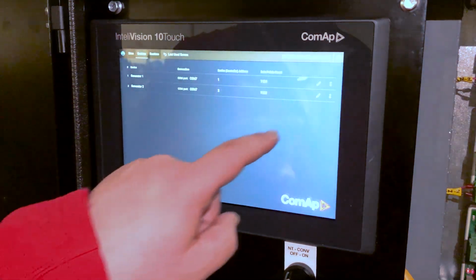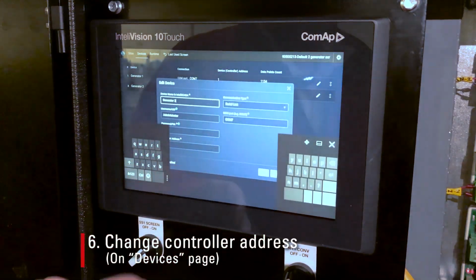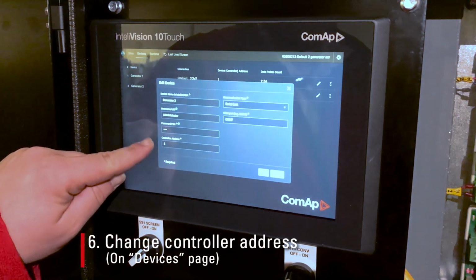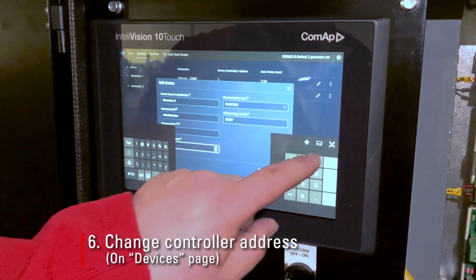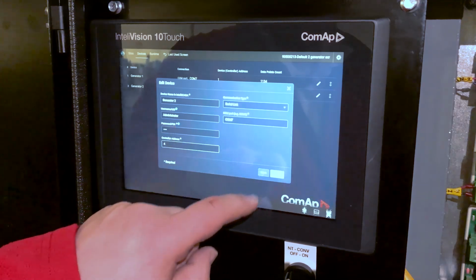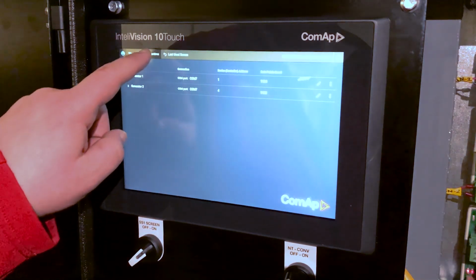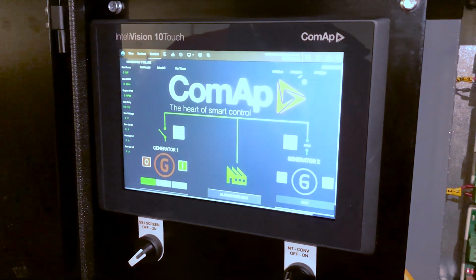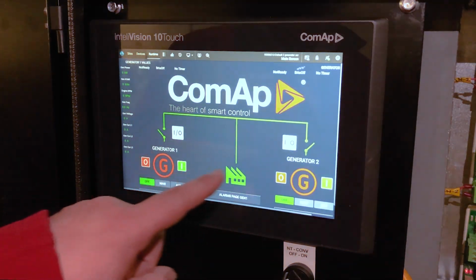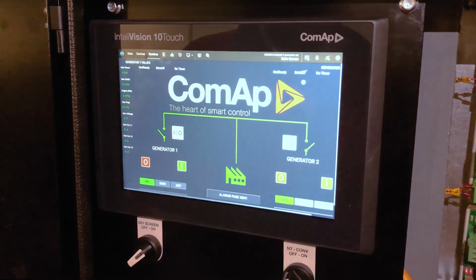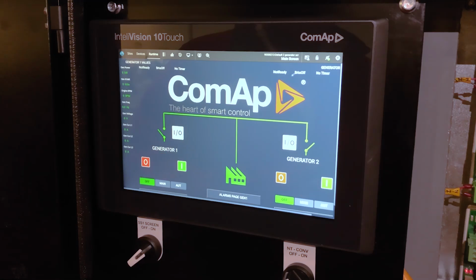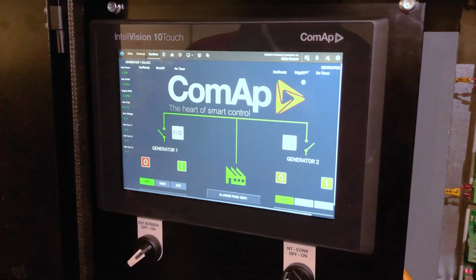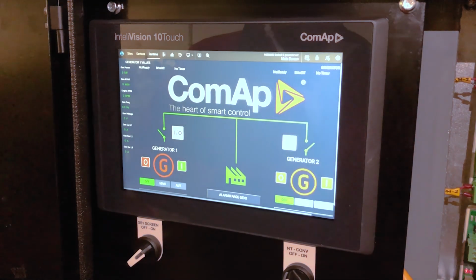The next step is to change the controller's address on the devices page. We will be replicating the same process as when we changed the controller addresses in the Set Points page step. In this example, I'm only changing the rear generator. Please note on the home screen, the indicators listed here do not change when the controller address is modified. Generator 1 corresponds with the front genset, and generator 2 corresponds to the rear genset.